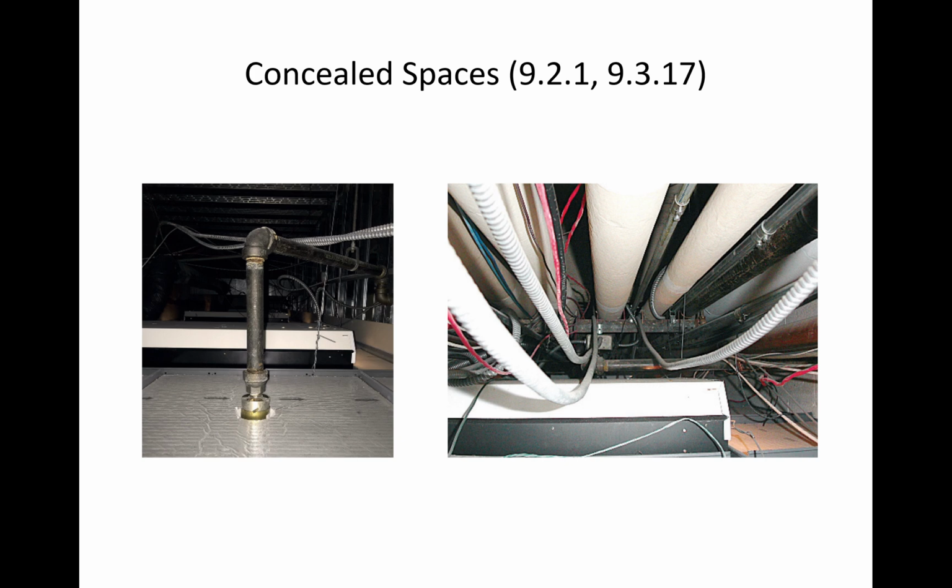First of all, the concealed spaces. Concealed spaces of non-combustible or limited combustible construction with minimum combustible loading having no access are not required to have sprinkler protection. And even spaces with small openings, like for return air, are also not required to have sprinkler protection.